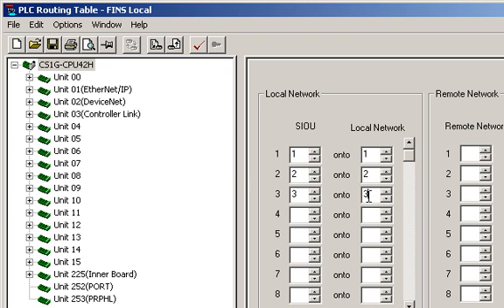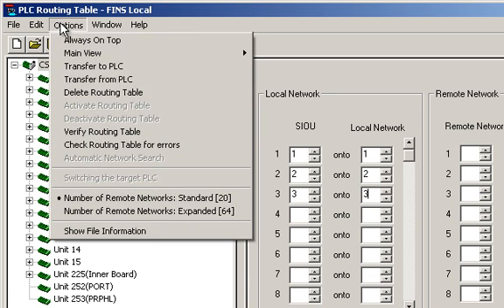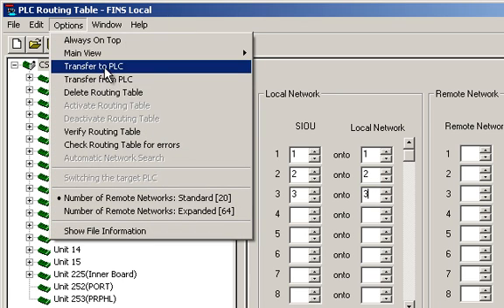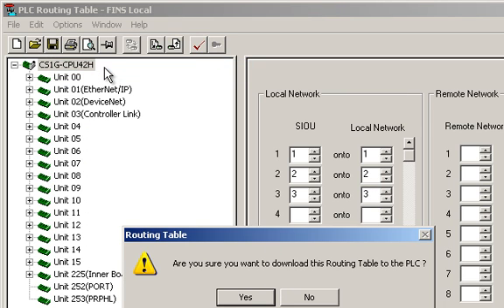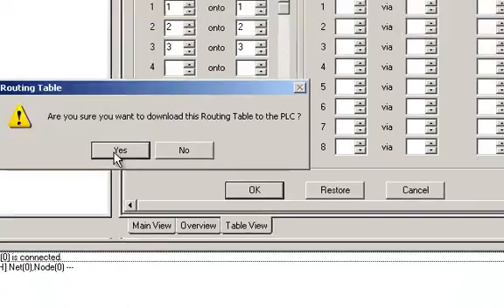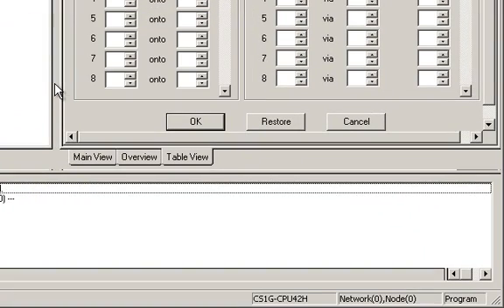Once you have entered the unit numbers and network numbers, all that is left to do is to transfer this to the PLC. To transfer down to the PLC, click Options, Transfer to PLC, click Yes to verify that you wish to download, and when the download is complete, you have completely transferred the routing table to the PLC.